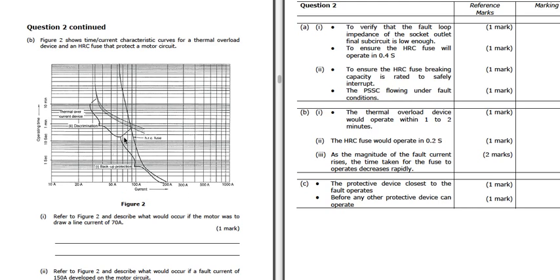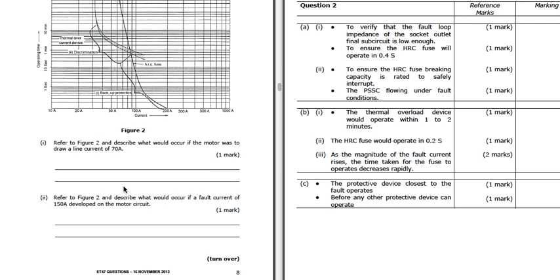So because that 70 doesn't touch the HRC fuse line, it's only touching the thermal overload line, that's what's going to happen. So within 1 to 2 minutes, that thermal overload is going to trip. If we get a fault current at 150, well, there's our 100 there, there's our 200. So 150 on a linear scale would be roughly in the middle, but because it's non-linear, it's going to be slightly off, but it's going to hit that HRC fuse there, and we go across here. It's going to be a very, very short time, only about 0.2 seconds. So it's going to be a much faster operation because the HRC fuse is going to operate.